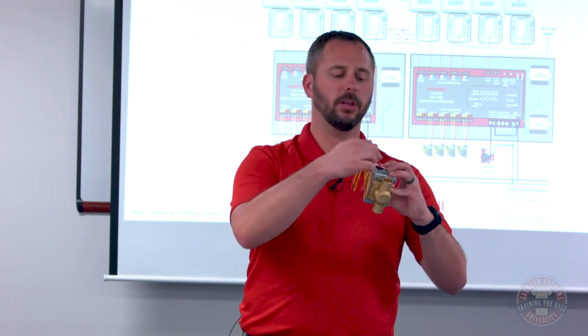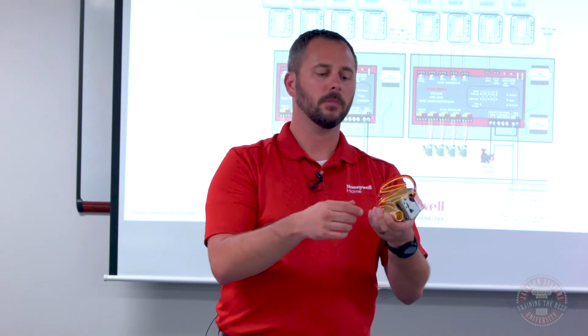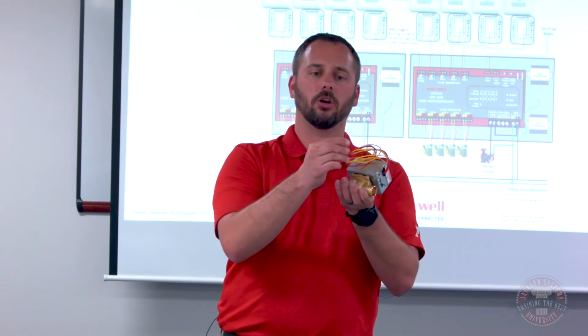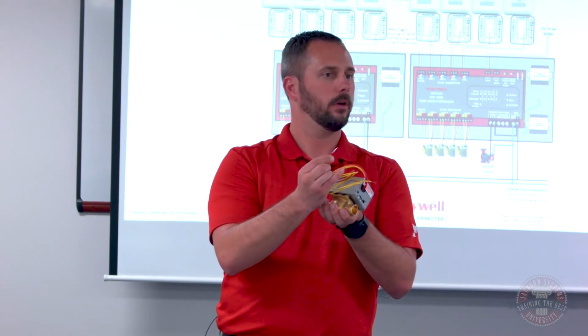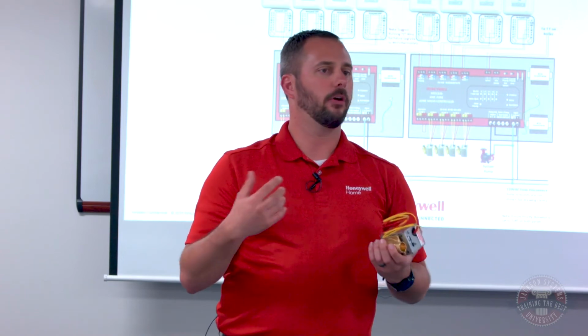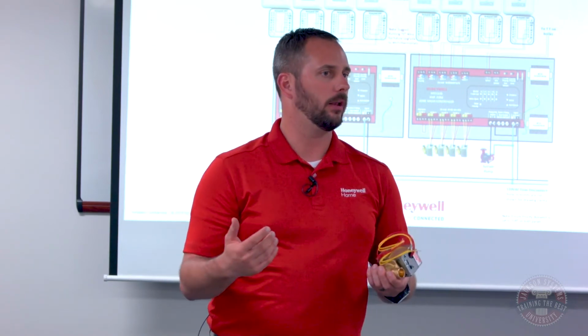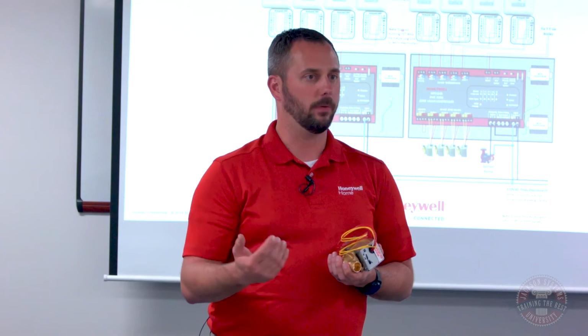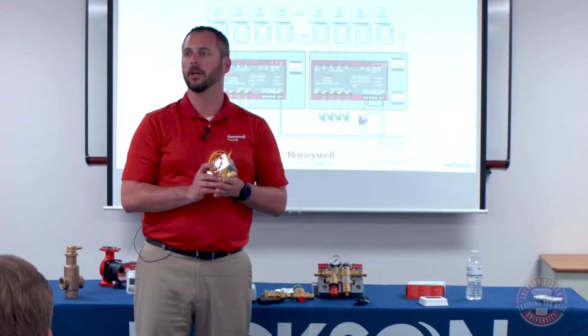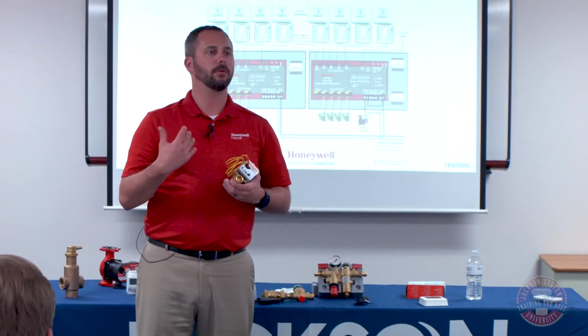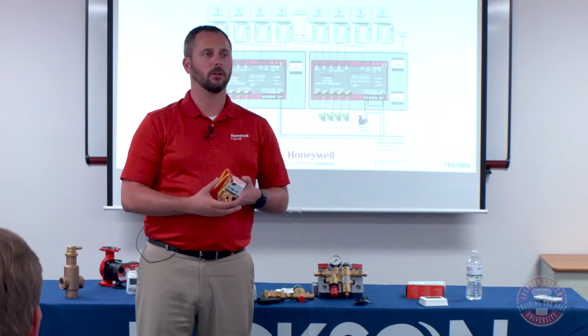So what happens is when this valve opens, it's going to close continuity across these 2 red wires here. The reason we do that is we don't want to turn a pump on or a boiler on if the valve is not indeed opened. It takes a couple seconds for these valves to open and close, so it basically builds in a delay and waits to make that contact closure.